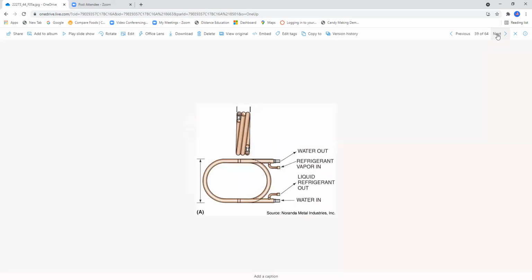Now here's something I used to work on a lot. This would be an example, and this is found on page 1329. And this basically is a coiled coaxial tube within a tube heat exchanger. The tubes are sealed in such a manner that the inside tube is separated from the outside tube. And basically you're going to circulate refrigerant one direction, water in the other. So basically what we're doing here again is we're utilizing a water source in order to remove the heat from the refrigerant.